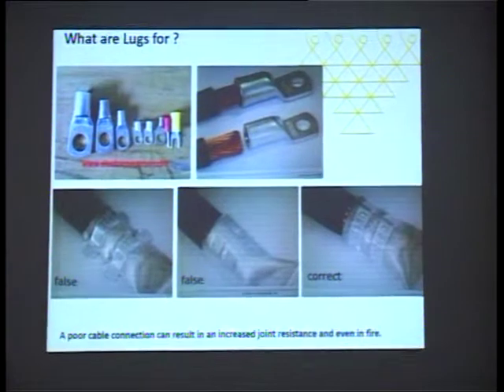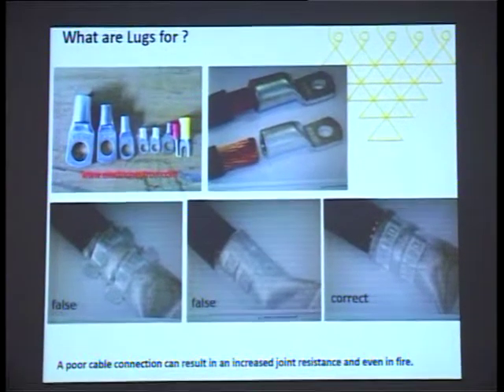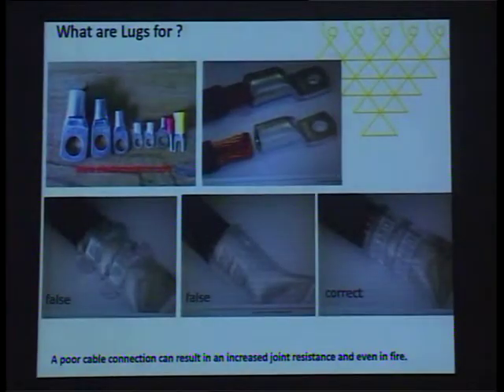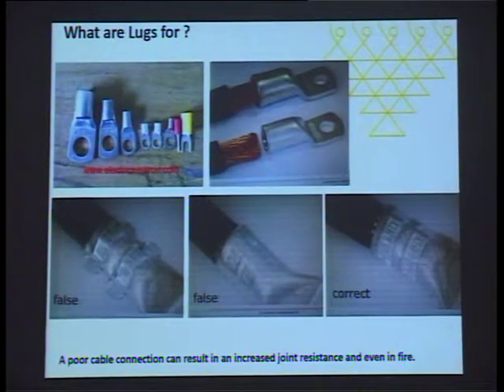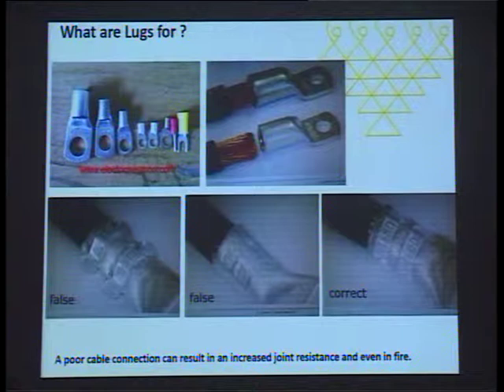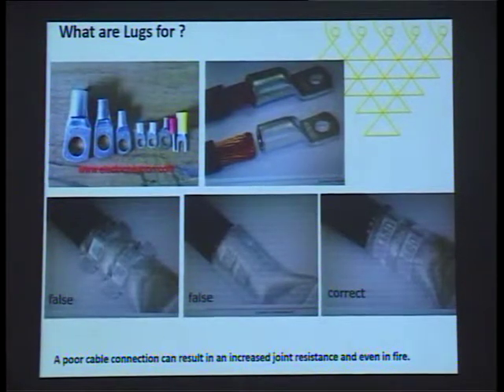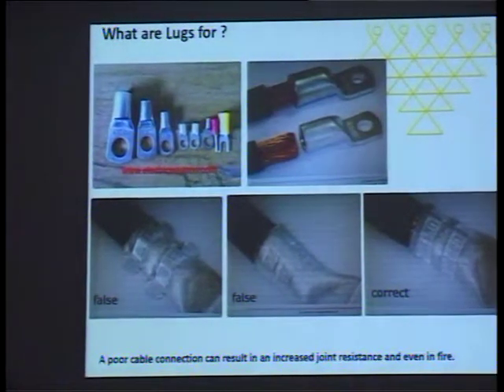You need to have special types of terminals for every cable. These special terminals are called lugs. And these lugs are not soldered or anything to the cable. You need to choose a proper size of lug. You need to put your cable inside that, and then there is a special tool which is called the crimping tool. Using this crimping tool, you have to press this lug against these wire connections, just to ensure that there is a firm connection in between, and then these lugs are directly tightened into the terminal strip. If the wrong lug is used, then it will probably increase the joint resistance, and it can limit the current, or whenever you need high power through this cable, the cable will not be able to supply it.